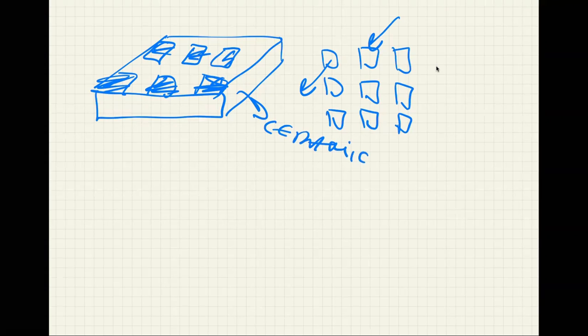However, this is not good, because if you are doing something to this element, the next element will also feel it. Why? Because it's a solid material. This element, if it oscillates in this direction, will also oscillate in this direction, and the next element will read part of the signal that the elements around it are feeling. So there will be a lot of crosstalk, a lot of coupling of the signals, and you will basically have a big noise.